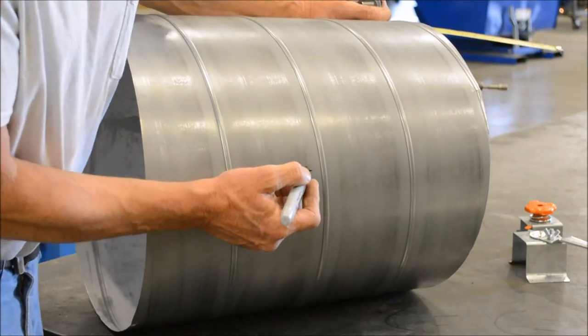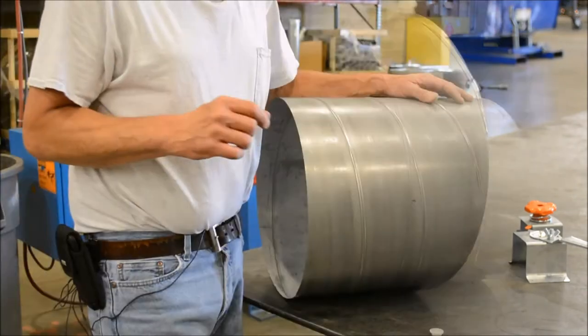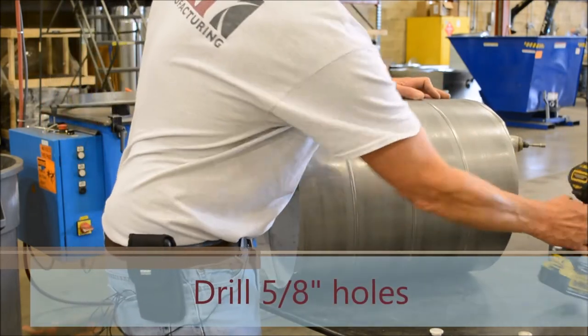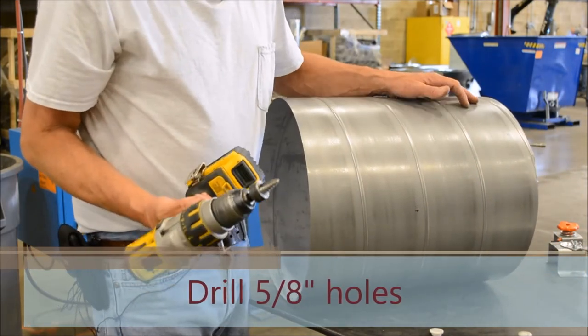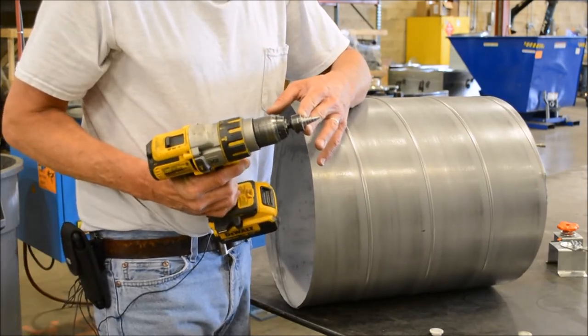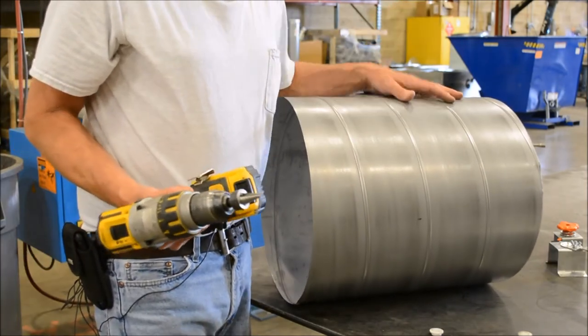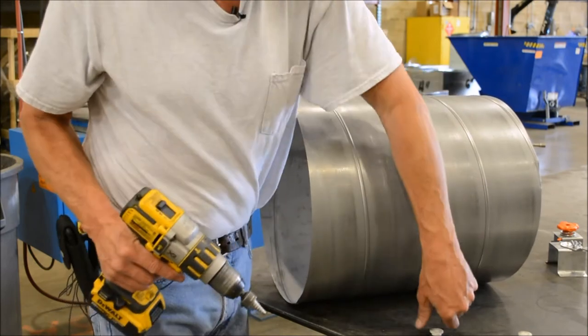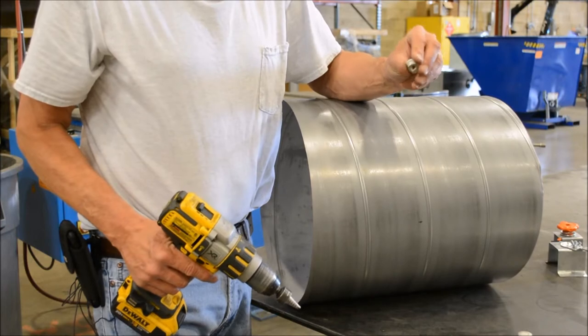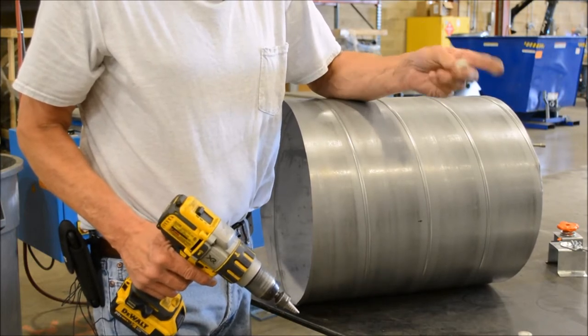There's where I'll be drilling my hole on this side. All right, next what we're gonna do is drill a five-eighth hole. We use the step bit, we got a stop on the five-eighth mark so we don't go any deeper than that. Our rubber grommets are actually low leak rubber grommets, so we use that on all of our single wall dampers.